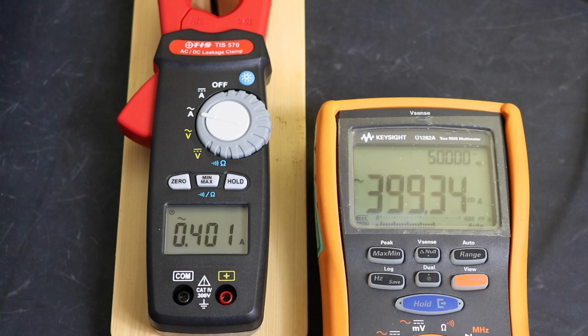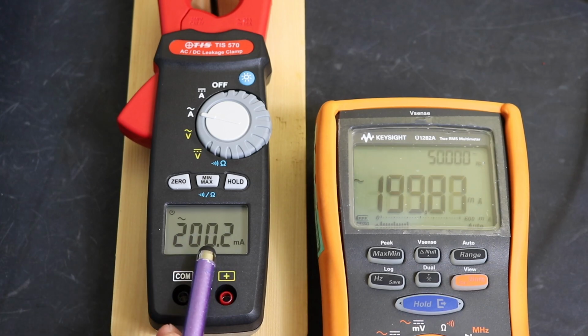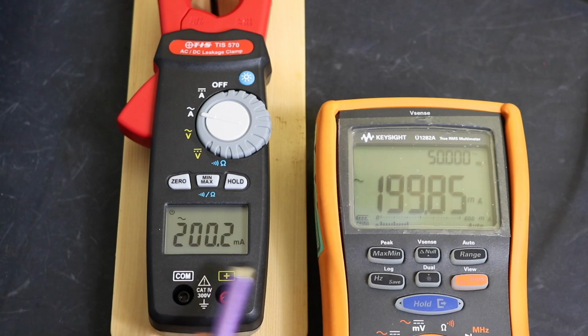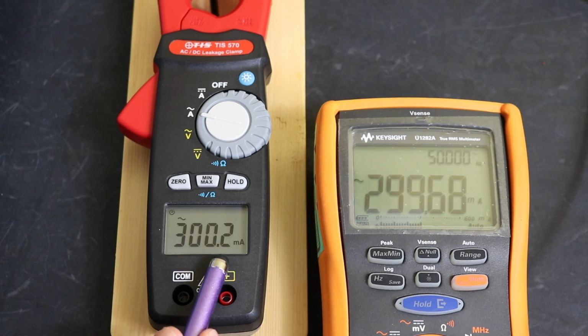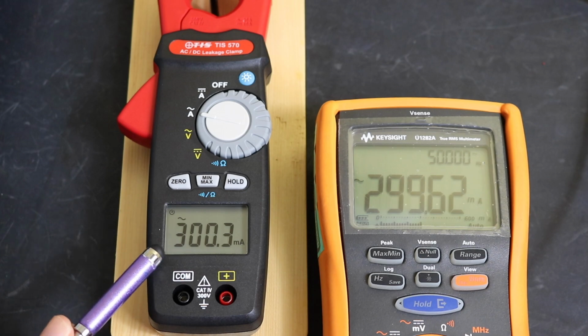If we go to 60 hertz, you can see there's no variation whatsoever, so we are all stable frequency wise. With regard to our range change, let's just go down to 300 milliamps there, go down to 200 milliamps, and you can see we've now changed range and we've got the extra resolution, the 0.1 milliamp resolution, 200.2 against 199.88. If I go back up to 300, you can see that we still retained our 0.1 milliamp resolution on this occasion. So when we're going up, we retain it. When we come back down, we stick at the 3-digit resolution, the 1 milliamp resolution. So it looks like our range changes around about the 300 milliamp mark.